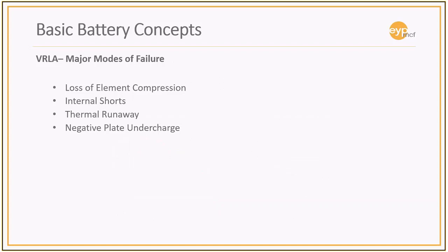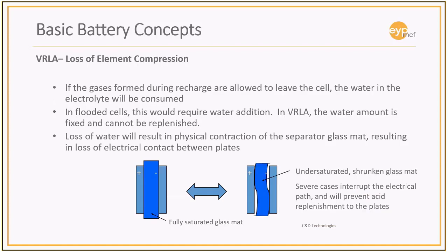We talked a little bit about the major modes of failure when we went over the different technologies, but ultimately internal shorts, thermal runaway, and negative plate undercharge are other issues associated with valve regulated batteries. There's a more in-depth description of the different failure modes and how they're affected in these slides and the video, but mostly the loss of element compression is due to the contraction of the separator plates, and you tend to lose capacity when this happens.